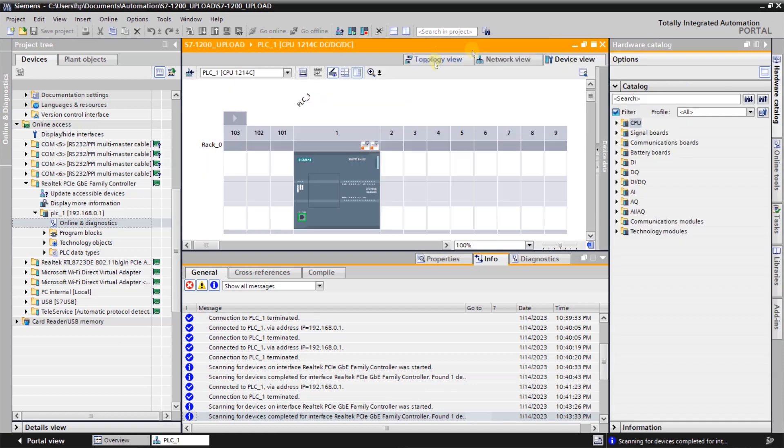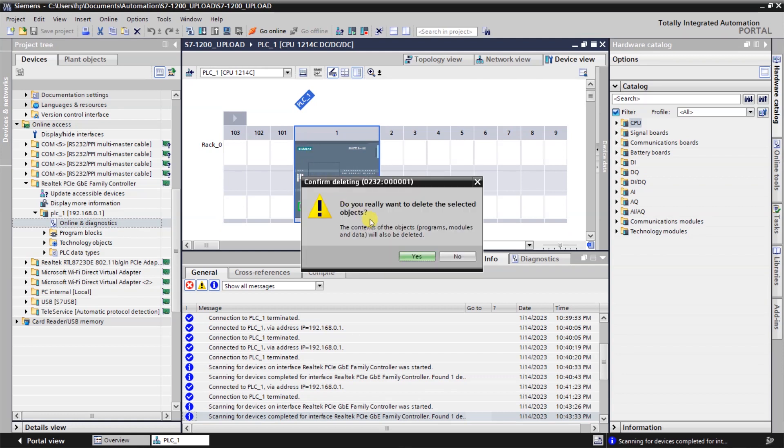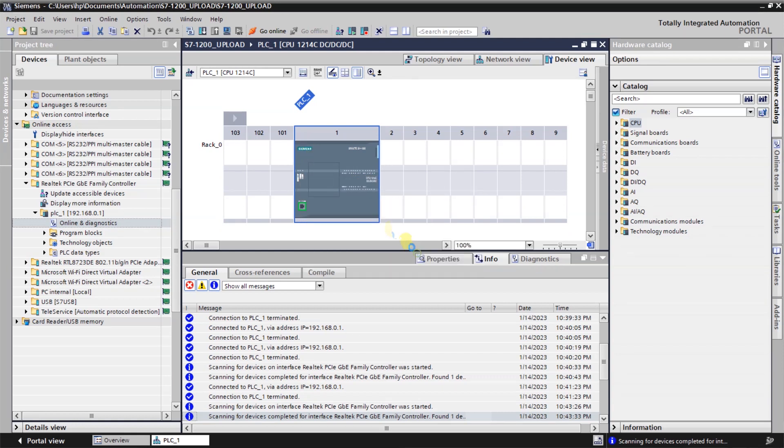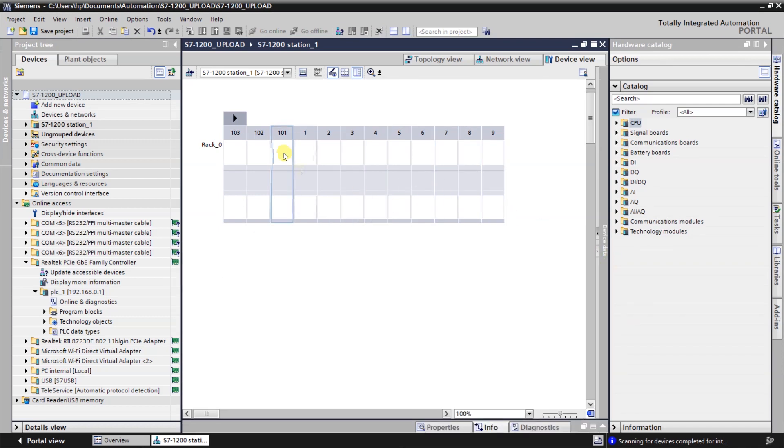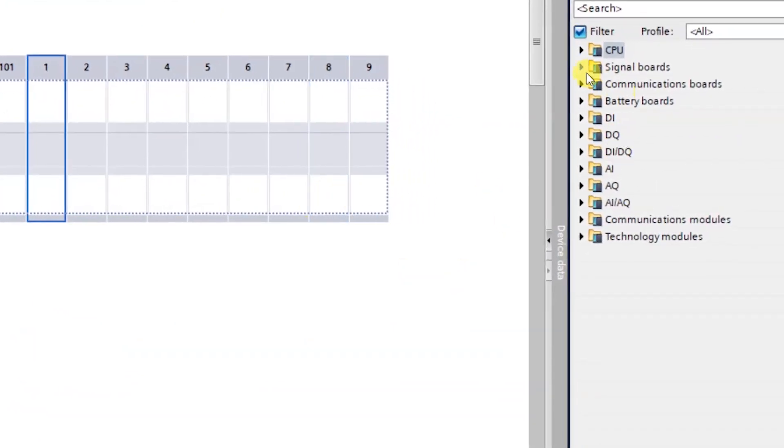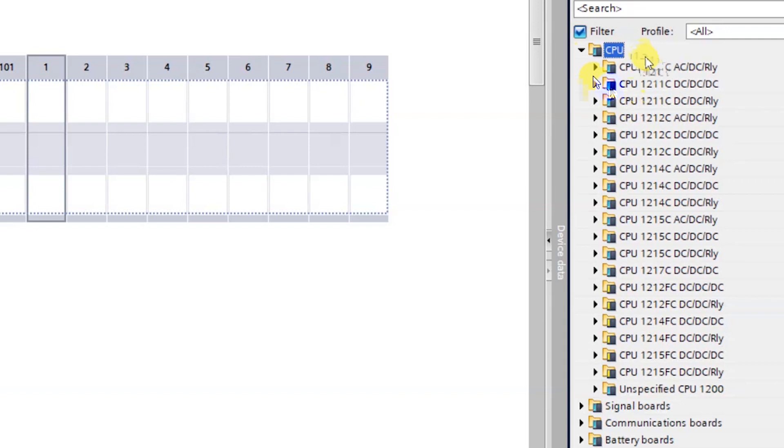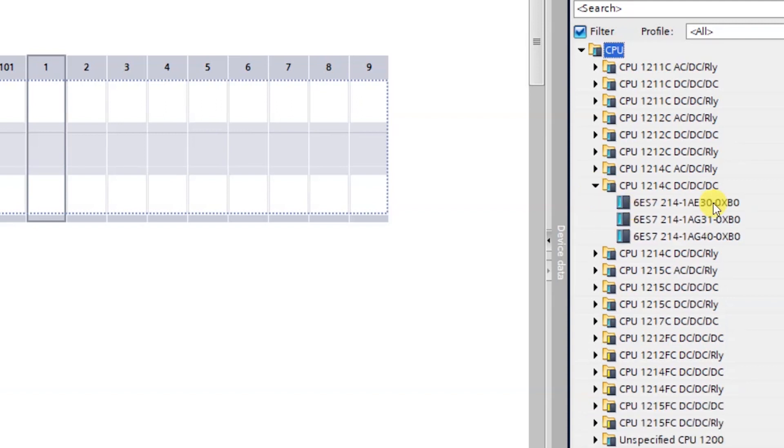We will go offline and we will configure the same PLC which has been shown in the online and diagnostics. We will delete this PLC and add another PLC in the hardware configuration. Just go to the catalog and from here you can select the CPU 1214C DC/DC/DC and select AG 40 here.